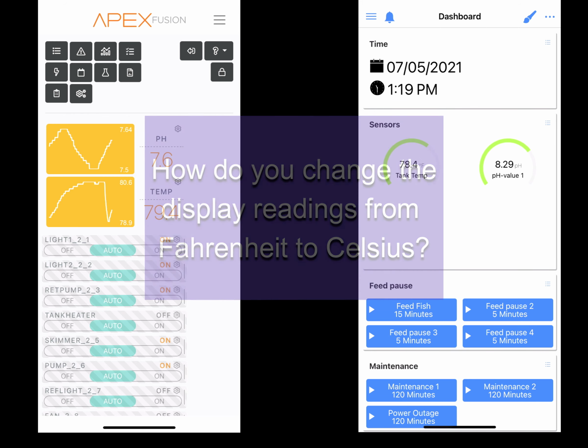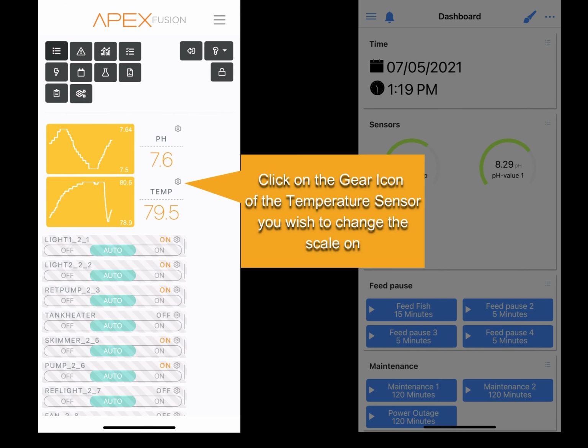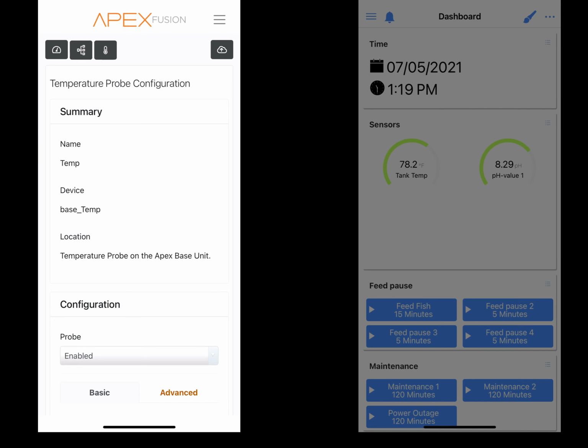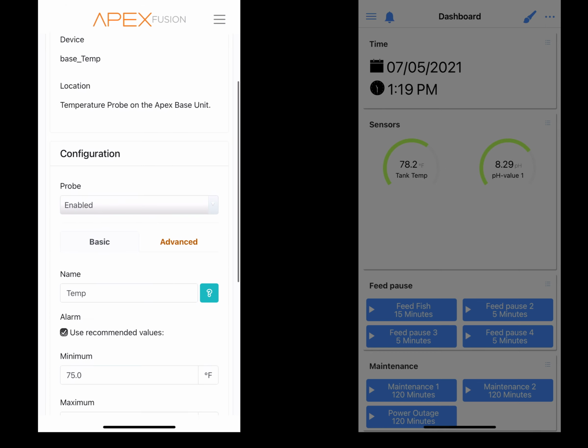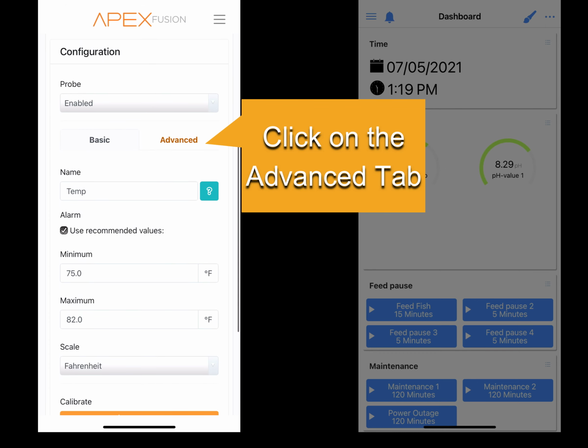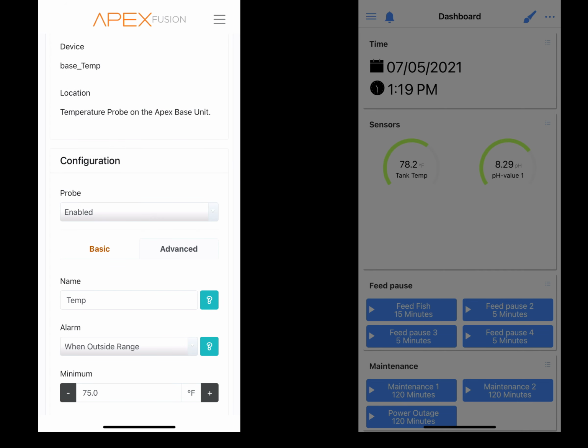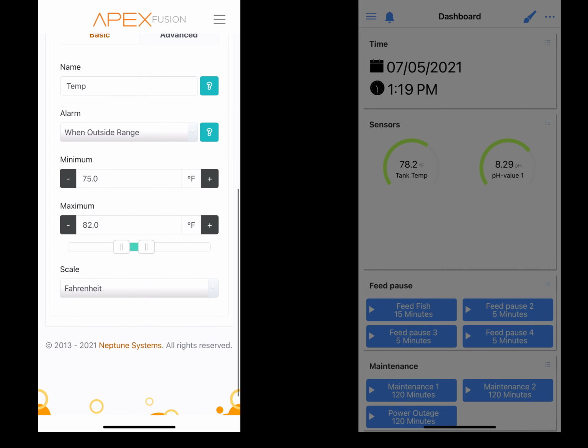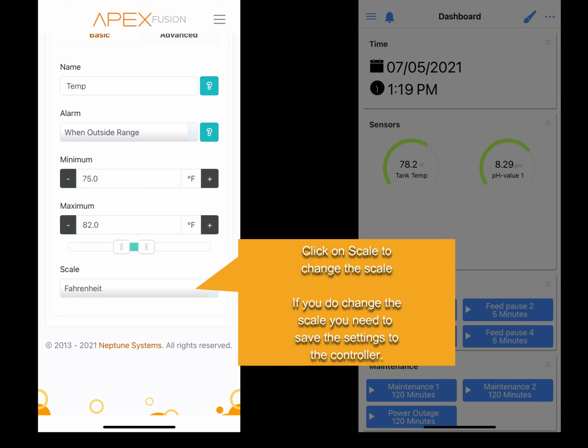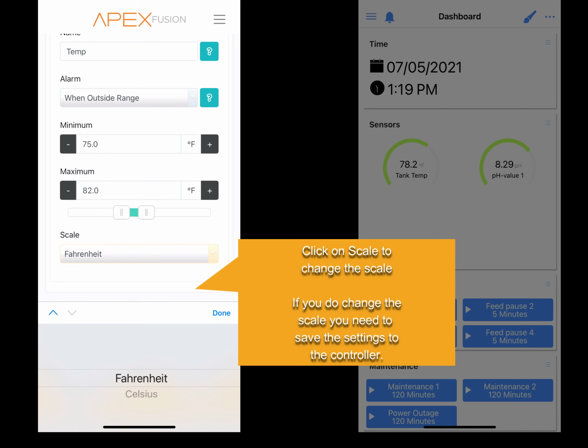How do you change the display readings from Fahrenheit to Celsius? On a Neptune controller, click on the gear icon next to the temperature sensor. Now that you're in the temperature probe configuration, you need to scroll down to the configuration section of the probe. Choose the Advanced tab and scroll back down and look at the scale. By clicking on the scale, you have a choice to choose Fahrenheit and Celsius.